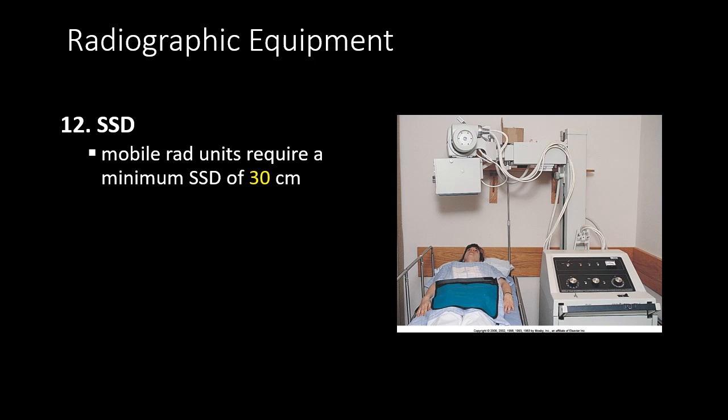Number twelve is the SSD, which stands for source to skin distance, the distance between the anode of the X-ray tube and the patient's skin. There is a minimum requirement of 30 centimeters, otherwise 12 inches.